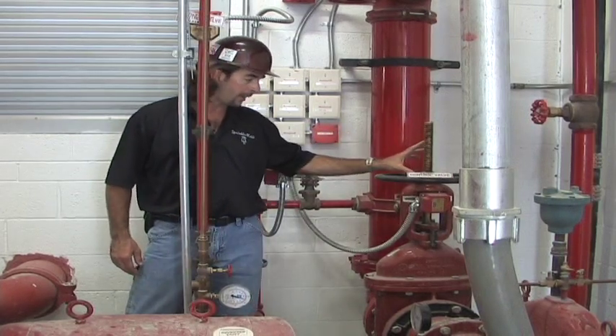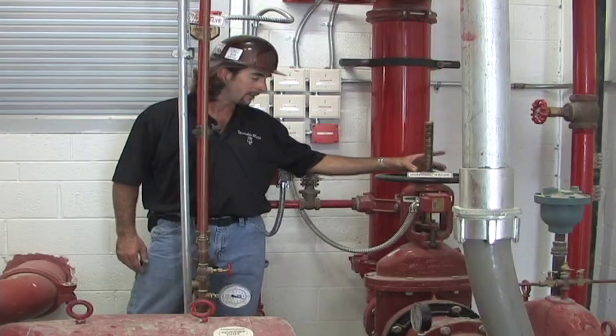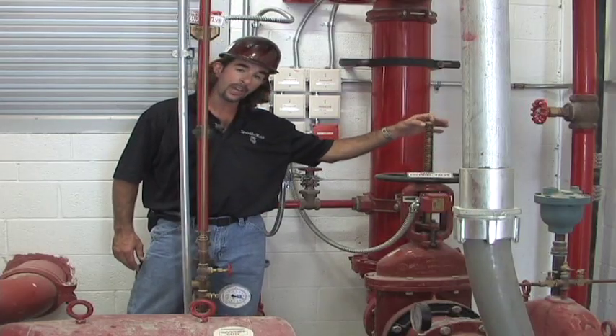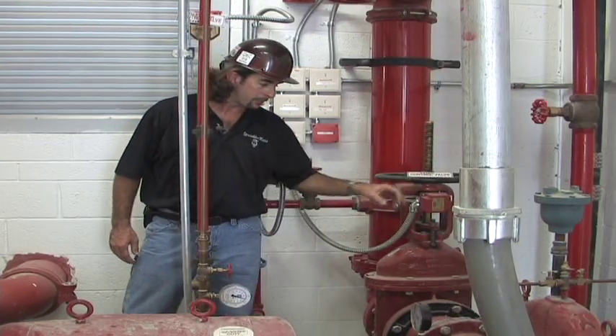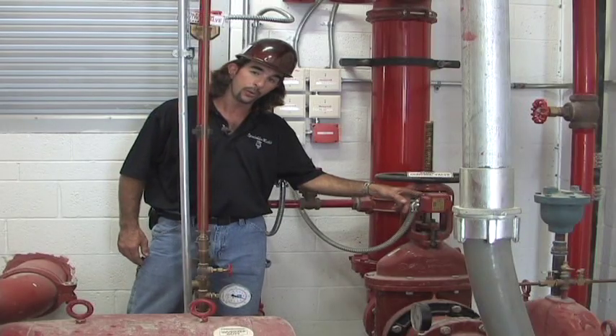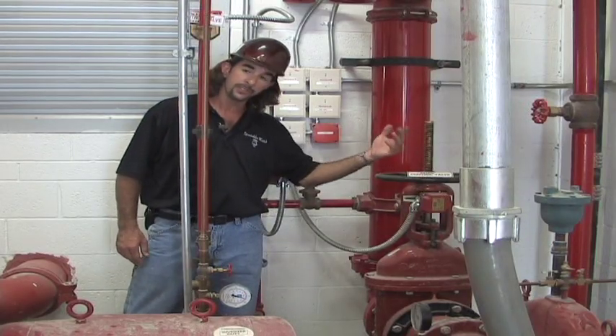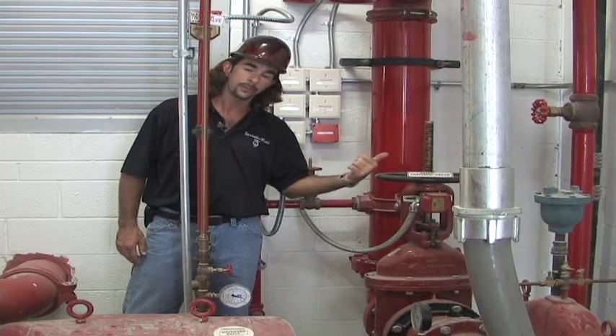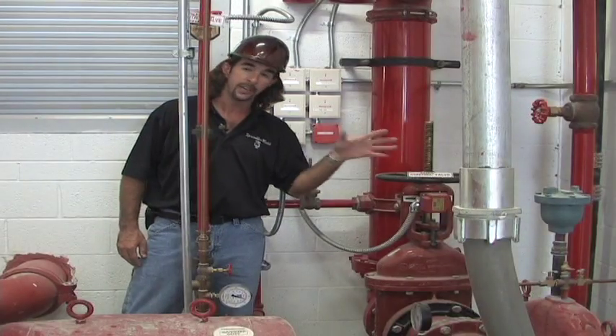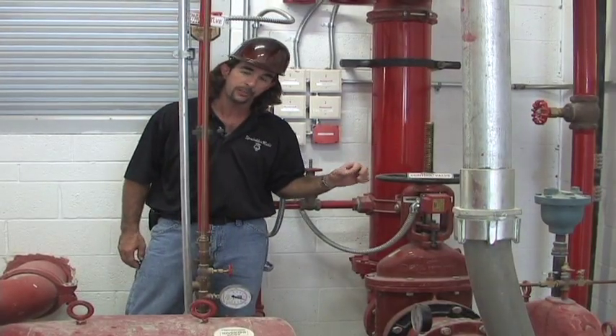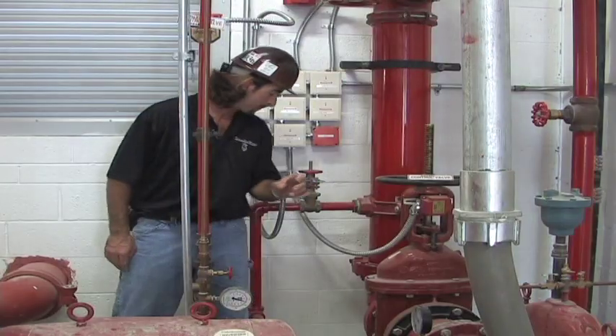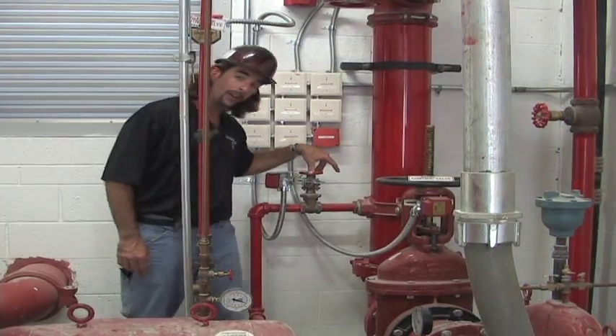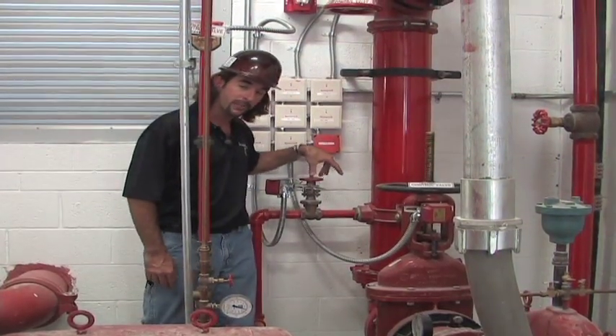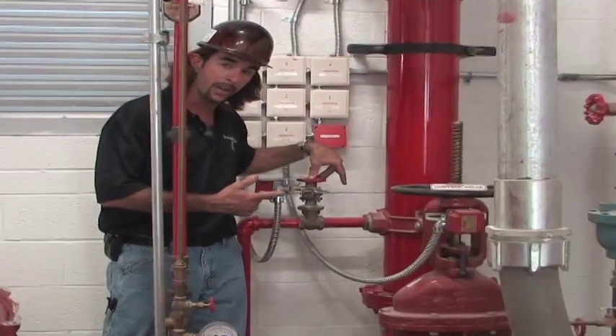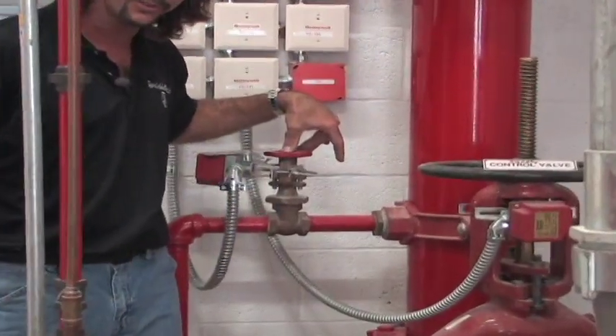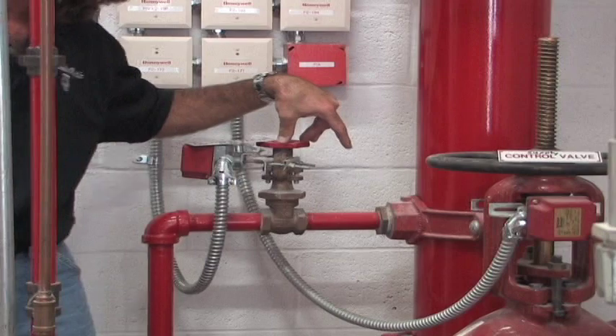All these valves that we have inside the pump room are all indicating. This is an OS&Y, which is an outside stem and yoke. Plus we have our tamper switch, which has a groove inside the stem. As soon as that valve is closed, the arm comes out of the groove and sends a trouble to the panel saying that the valve is closed or partially closed. Same with the OS&Y that we have for our Jockey pump. It's got a groove in the stem. When the arm comes out of the groove, we would get a trouble to the alarm panel.